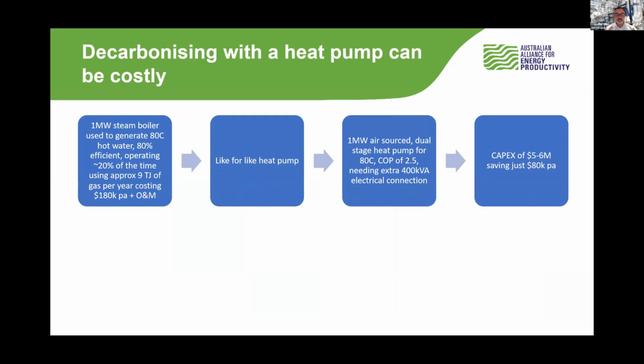So what is the impact of this webinar and these tools? I thought the best way to show that is in dollars. Let's take a standard base case: a 1 megawatt steam or hot water boiler used to generate 80 degrees hot water, 80% efficient. If you're lucky, the overall system is probably less than that. Typical operating utilisation for a boiler is about 20% of the time. That would use about 9 terajoules of natural gas per year, costing somewhere around 180K of gas plus O&M on top of that. So that's the base case.